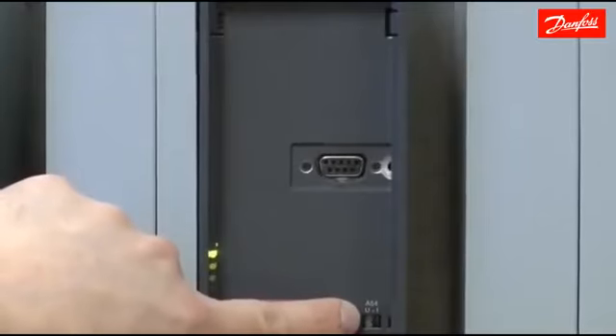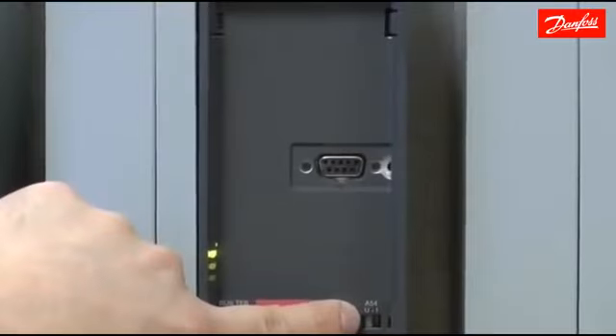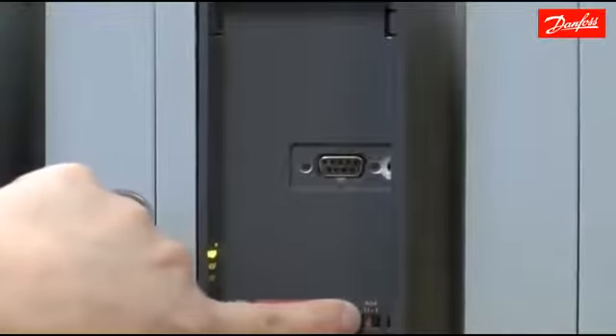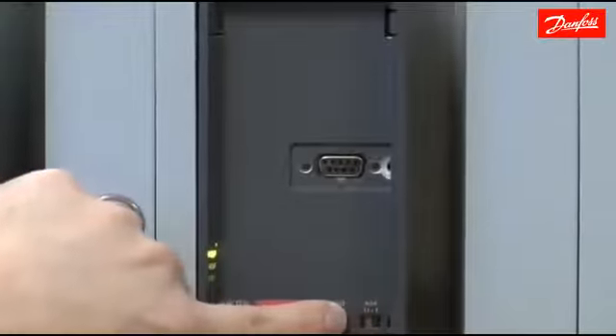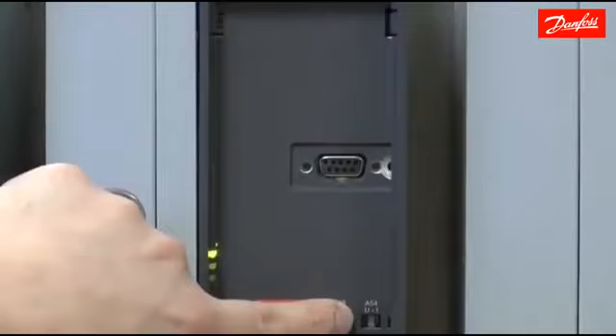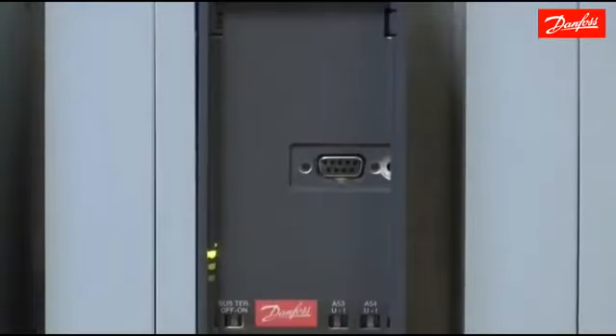Since I've chosen a feedback unit of 4 to 20 milliamps at analog input 54, I need to gently move the dip switch to the current position on analog input 54. You can accomplish this with a screwdriver and just a slight pry, and it'll move into the current position. You have to be careful because those switches are brittle.